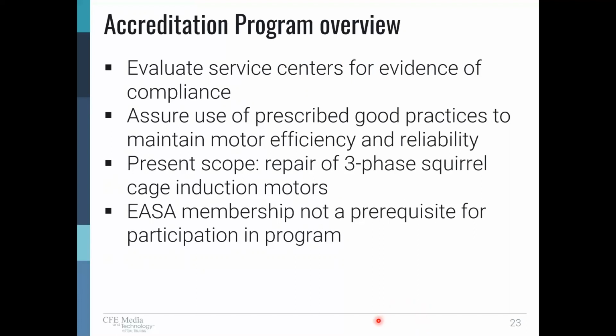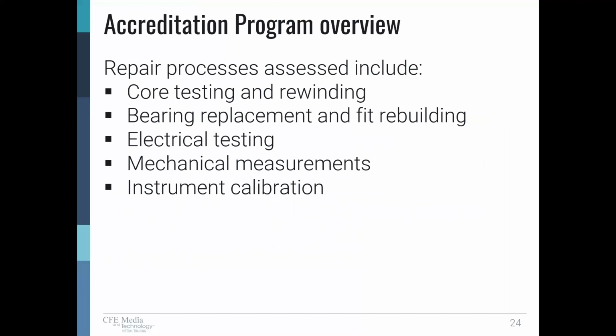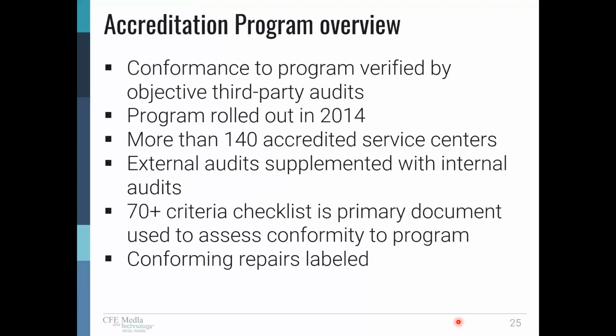And EASA membership is not a prerequisite for participation in the program. So a service center doesn't have to be an EASA member. So anyone with a service center anywhere in the world can get into the accreditation program. The major processes that we look at: core testing and rewinding, bearing replacement, fit rebuilding, electrical testing, mechanical measurement. So we've got basically a test and measurement, electrical and mechanical. Instrument calibration is also an important aspect. You can get someone who can measure accurately, but if the device they're using for the measurement isn't accurate, then you don't have a good result.